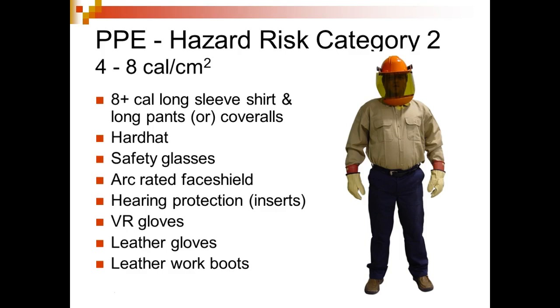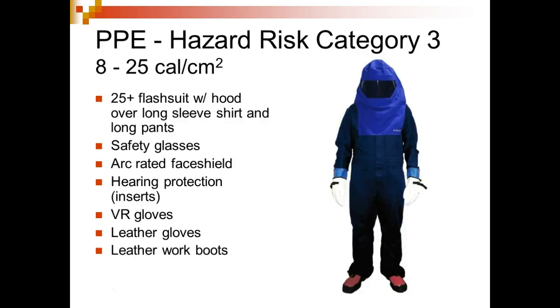Hard hat, safety glasses, arc rated face shields, hearing protection, voltage rated gloves, which means your gloves have to be rated for whatever voltage you're going to be working in, or the highest voltage you'll encounter. This is 8 to 25, category 3: 25+ flash suit with hood over long sleeve shirt and long pants, safety glasses, arc rated flash shield, hearing protection, voltage rated gloves as undergear, then leather gloves on top of that, and leather boots.